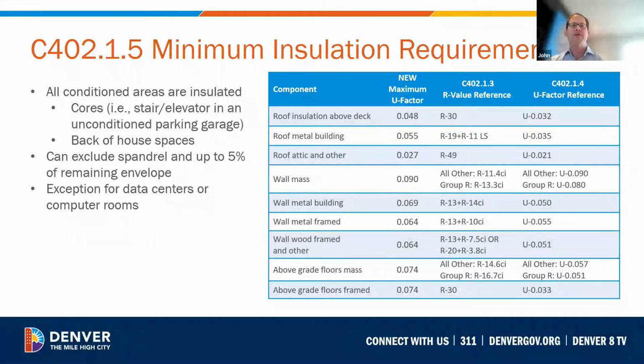So you notice at the table here, the new maximum U factor, and now this would apply both to prescriptive and performance levels, is a little bit less stringent than the existing prescriptive requirement, but it's intended to limit the trade-offs to ensure that all projects have a minimum level of envelope performance, since often those envelopes aren't updated or altered during their building's expected life.